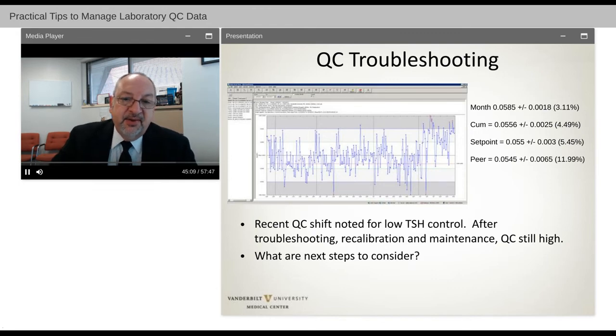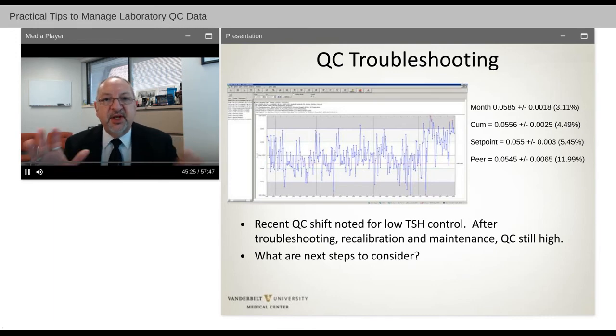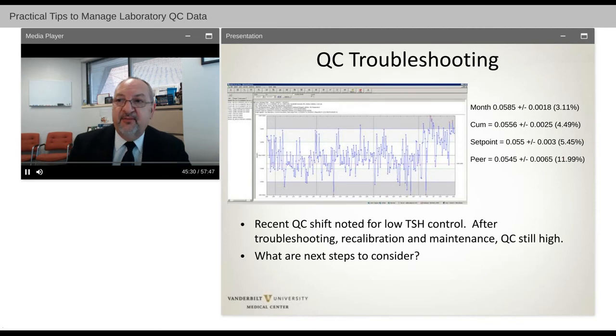Now, we also want to look at setting our ranges too tight. We want to be careful because we may be troubleshooting too often or too frequently, and this is a waste of resources. So part of a peer comparison is readjusting, making sure that you're matching your means, your peers out there, and not just that the mean is matching, but that your standard deviations or coefficient of variation in terms of the width of your ranges is reasonable.